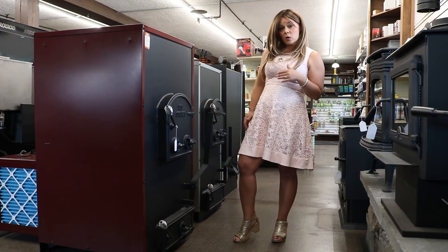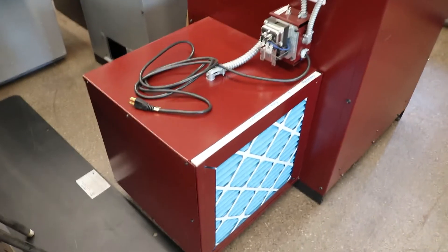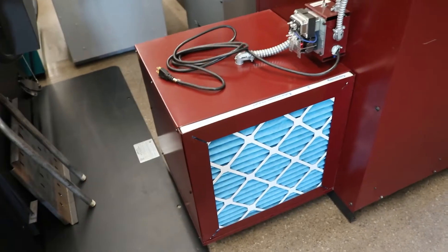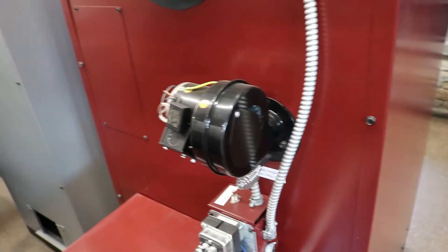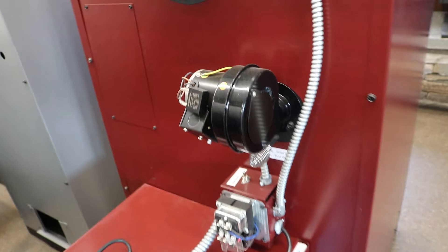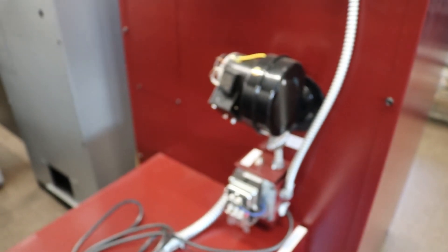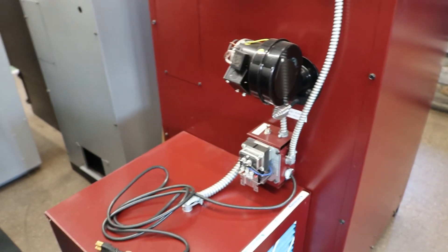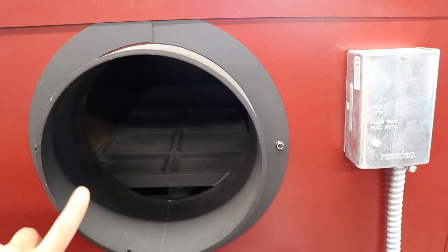I'm going to take you guys up close and show you inside the firebox and around the rear of the unit. Here we have the backside blower cabinet, which comes with the filter and the box. This is going to be your blower for your draft, and the draft blower does need to be wired in. This draft blower operates on a thermostat — it will not kick on automatically, so you do have to have it on a thermostat; it'll hit a certain temperature before it activates. Here we have the DS-300 Cozy King model, with a rear flue — this is going to be an eight-inch flue on this particular model.